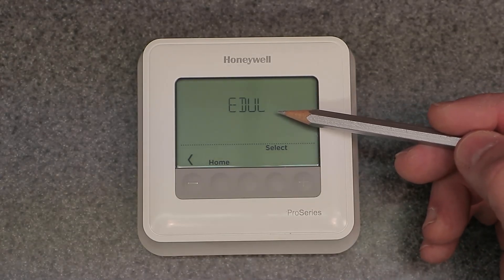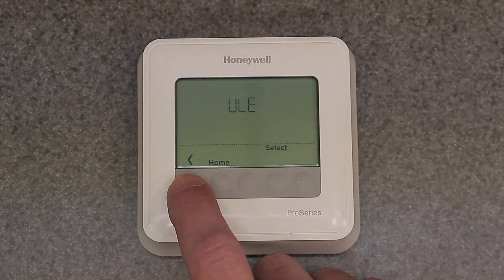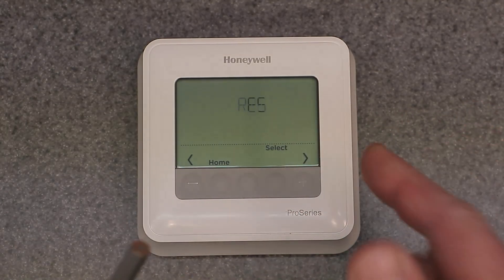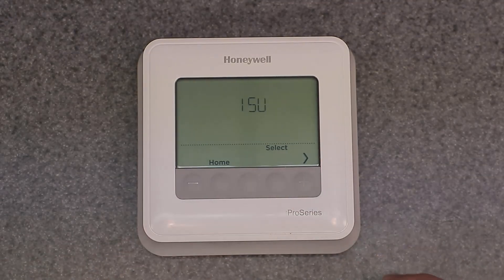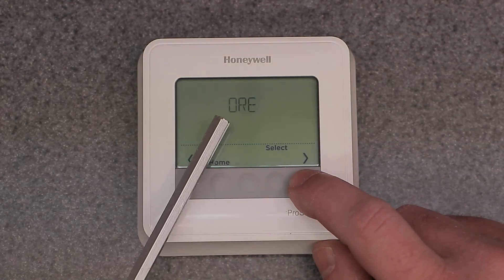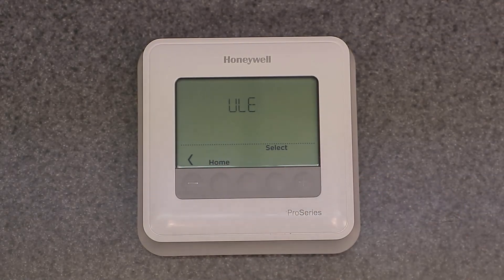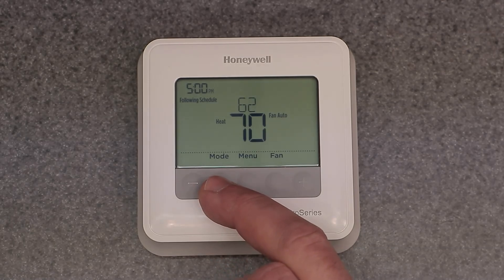You have two options: restore just the schedule, or restore the entire thermostat completely — that's up to you. You access it by holding those two buttons, getting into the ISU menu, going right past Test to 'Restore Defaults,' and right once more for 'Restore Schedule.' Once done, go to Home and it brings you back to the main screen.